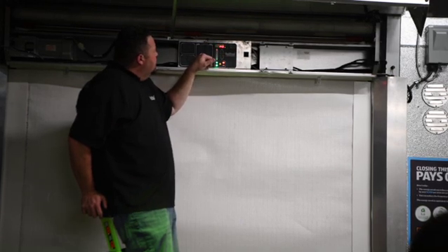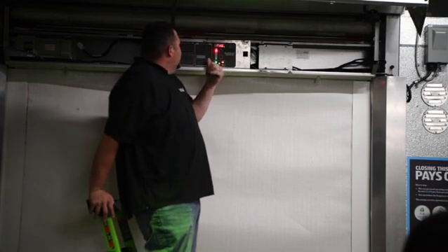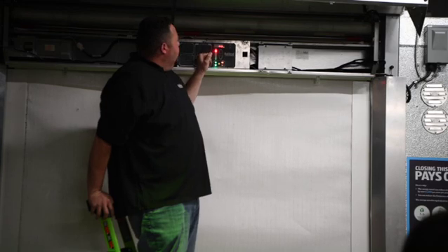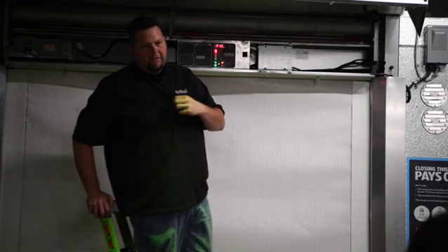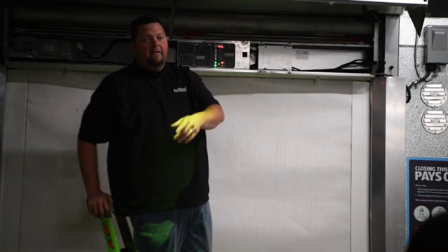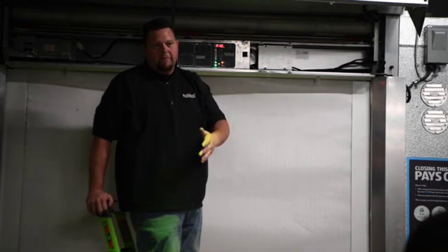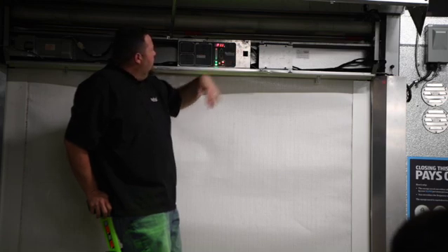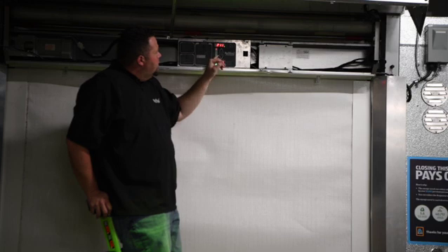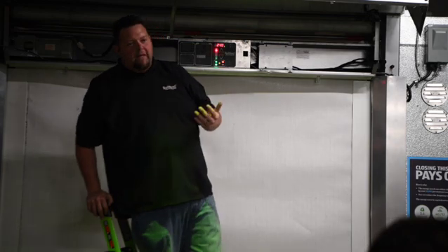P10, service cycle reset. It's on no. So P11, the next setting is like if you were to do a preventative maintenance. We don't have anything telling you to do preventative maintenance, but if you guys decided, hey, your door hits 100,000 cycles, we just want to make a trip to look at it, whatever it may be, you can set that. So the next one is P11, which is your service reminder. Right now it's set for a service reminder to tell you at 240,000 cycles, but you can adjust that.